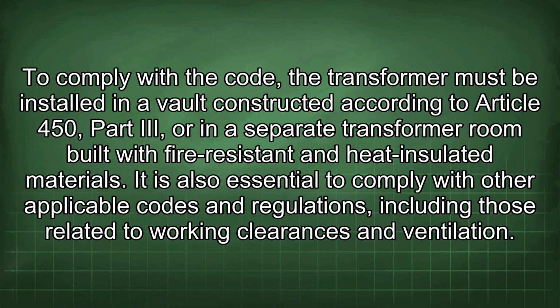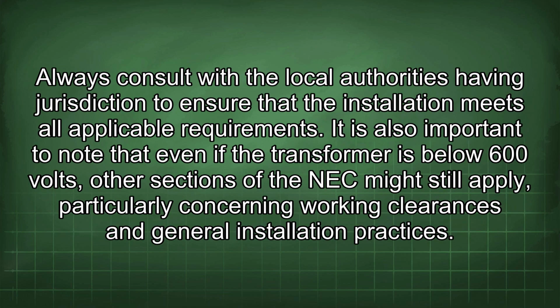To comply with the code, the transformer must be installed in a vault constructed according to Article 450, Part III, or in a separate transformer room built with fire-resistant and heat-insulated materials. It is also essential to comply with other applicable codes and regulations, including those related to working clearances and ventilation. Always consult with the local authorities having jurisdiction to ensure that the installation meets all applicable requirements. It is also important to note that even if the transformer is below 600 volts, other sections of the NEC might still apply, particularly concerning working clearances and general installation practices.